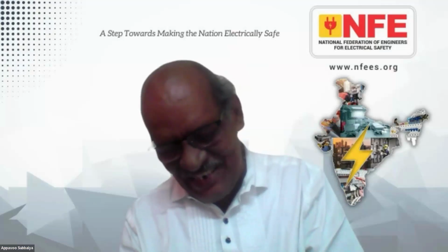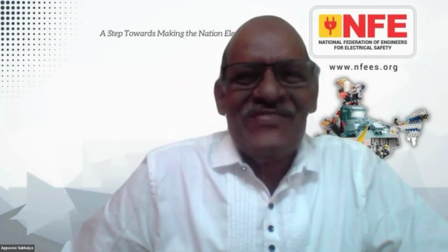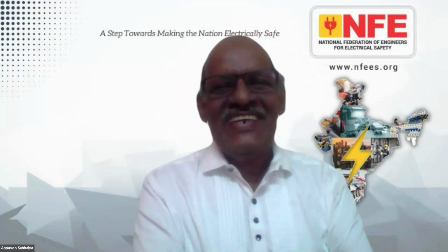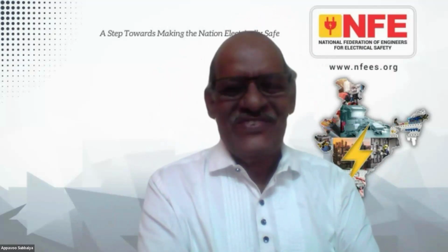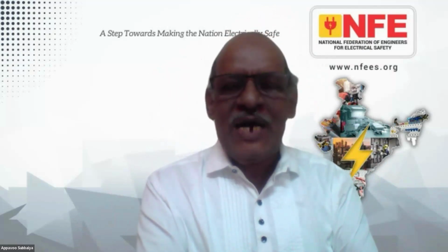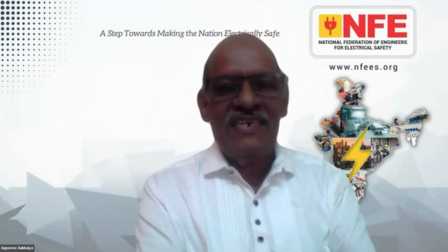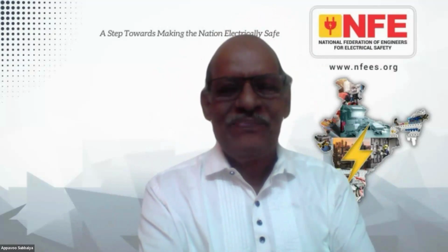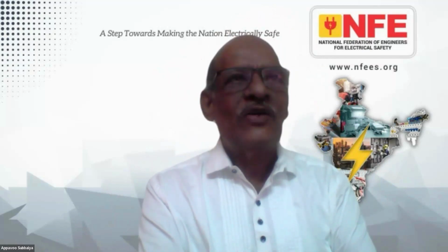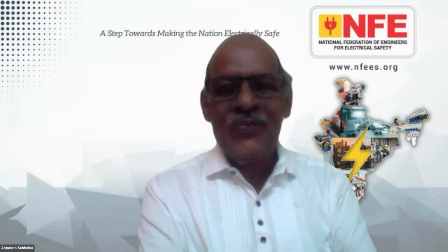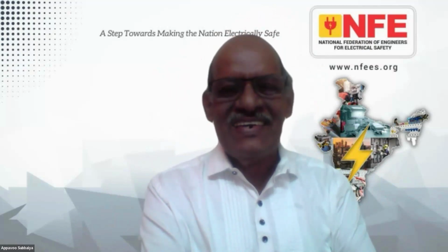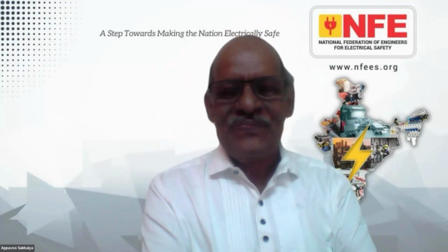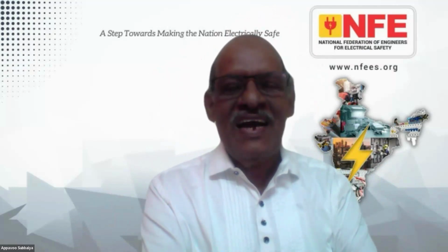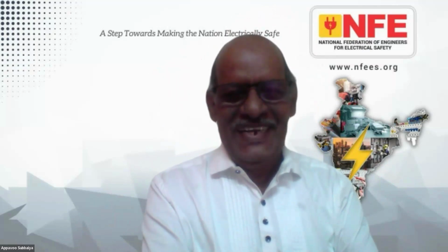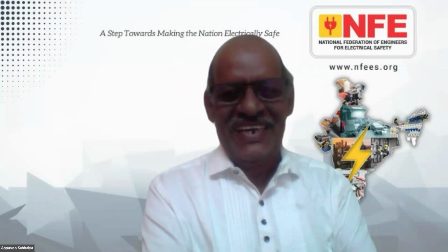You are right in one way. There are different views among panelists, but I may also differ from both of you, because recently I had an opportunity where a privately owned hospital - a relative of mine - had a 250 kVA transformer station. The load break switch failed and it shorted. Luckily no people were involved, but ultimately the supplier's installation got damaged, and they had to pay a penalty of more than the cost of the breaker itself.